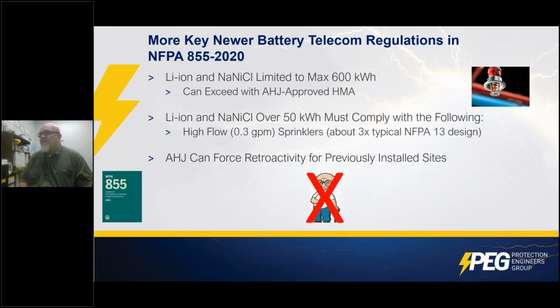There are a few more in 2020. Lithium ion and sodium nickel chloride were limited to a max of 600 kilowatt hours. The AHJ can approve larger installations, and obviously there are much, much larger installations in the energy storage world, but they have to have a hazard mitigation analysis plan, which usually means they put them outdoors in steel containers separated by anywhere from 10 to 13 feet typically, so they're not worried about the spread so much. Lithium ion and sodium nickel chloride over 50 kilowatt hours have to have high flow sprinklers installed. It's about 3 times the typical NFPA 13 rate.